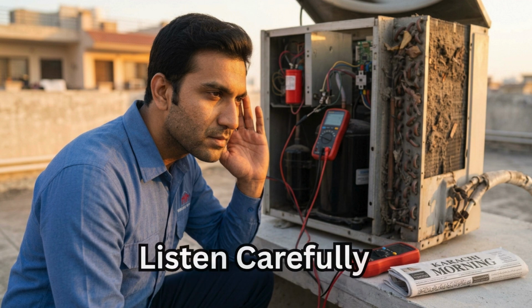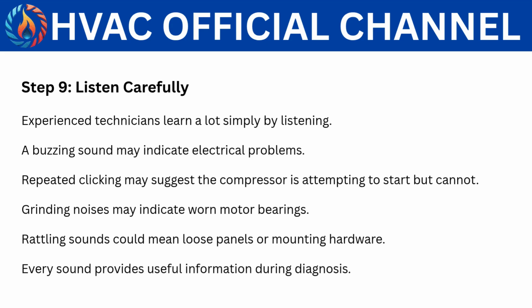Step 9. Listen carefully. Experienced technicians learn a lot simply by listening. A buzzing sound may indicate electrical problems. Repeated clicking may suggest the compressor is attempting to start but cannot. Grinding noises may indicate worn motor bearings. Rattling sounds could mean loose panels or mounting hardware. Every sound provides useful information during diagnosis.